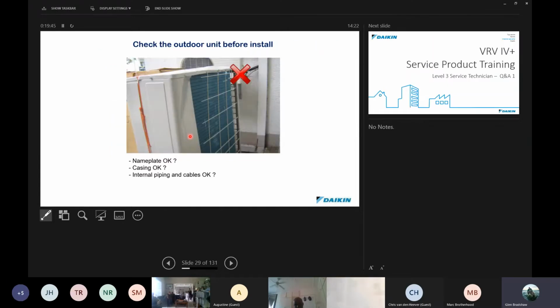Right, so when a technician receives a unit on site to install, a couple of things that he needs to have a look at. He needs to check that the nameplate is okay, so all the details in the nameplate are there. It hasn't been scratched off or anything like that. The casing is okay. In other words, we don't want to see casings that are dented and all that. If the unit's received like this, you need to report it.